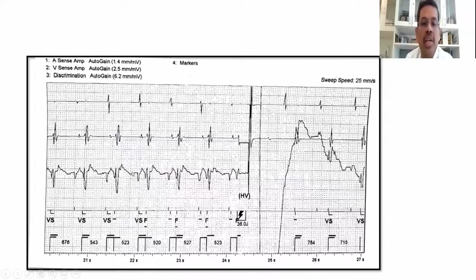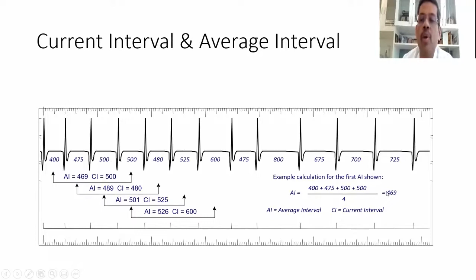Now, the way the Abbott devices diagnose ventricular fibrillation and ventricular tachycardia is by looking at the current interval and the average interval. The current interval is the RR interval being looked at, and the device also looks at the average interval of this current interval plus the preceding three intervals. So for example, here the current interval is 500 and the average interval is the sum of all these four intervals divided by 4, which is 469.